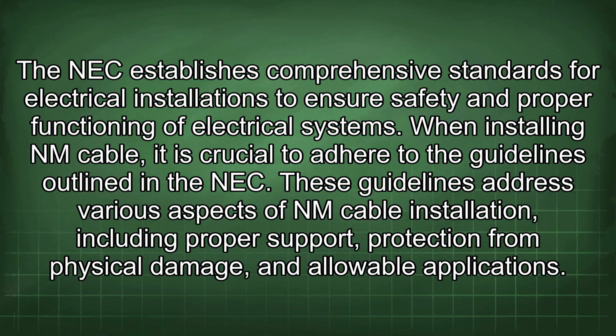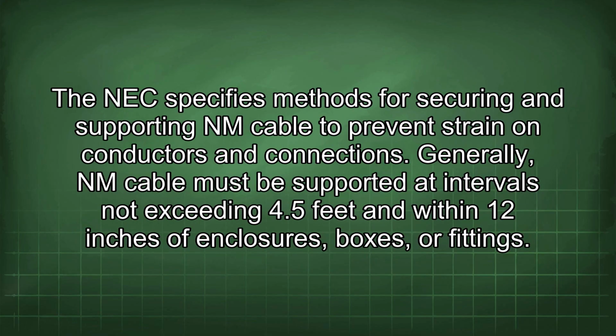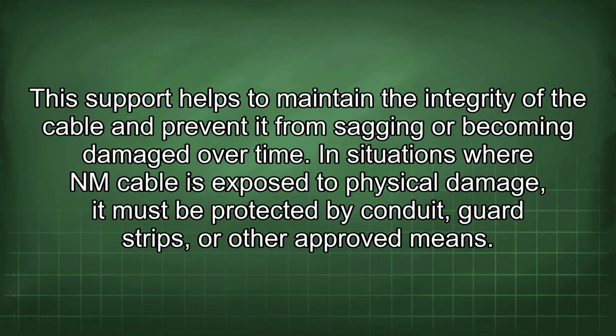These guidelines address various aspects of NM cable installation, including proper support, protection from physical damage, and allowable applications. The NEC specifies methods for securing and supporting NM cable to prevent strain on conductors and connections. Generally, NM cable must be supported at intervals not exceeding 4.5 feet and within 12 inches of enclosures, boxes, or fittings. This support helps to maintain the integrity of the cable and prevent it from sagging or becoming damaged over time.